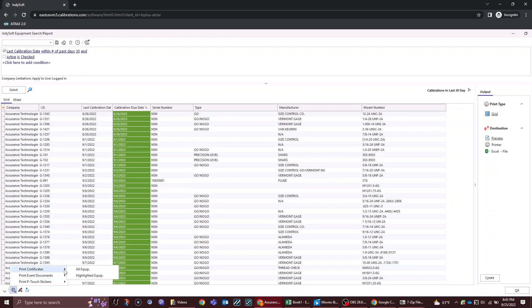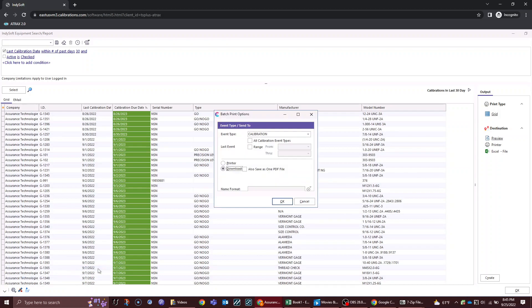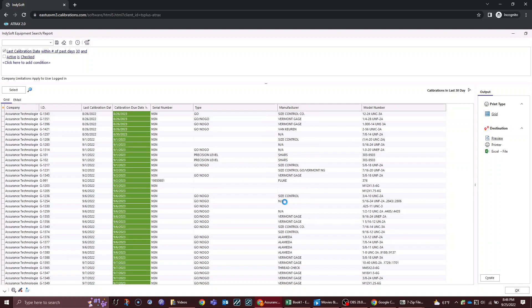Print certificates, and in this case I'm going to select all equipment. You could highlight equipment if you just want to grab certain chunks. I'm going to download the calibration events and I want to download them to a zip file. You could select send them directly to your printer. In this case I just want to download to a zip file.